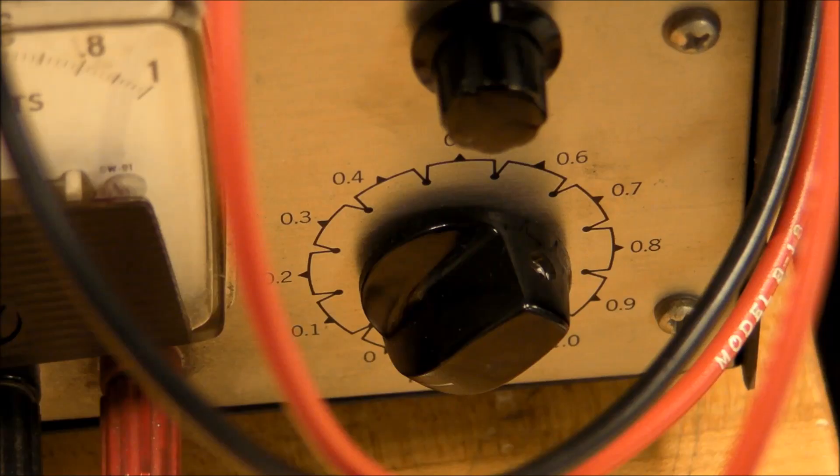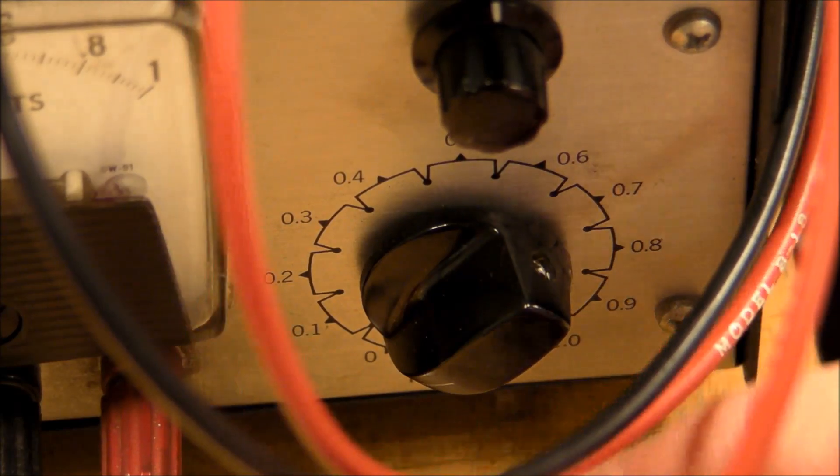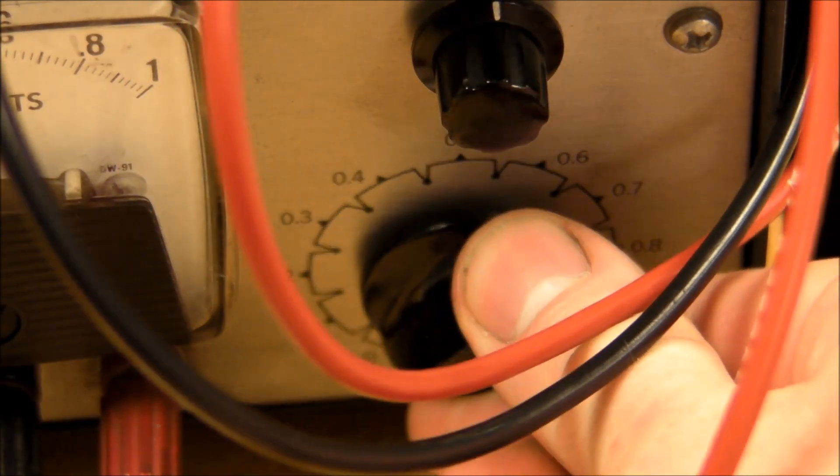Had a little problem there. I got to 125 volts and that was the end of the range. So let me, I already turned down the fine adjust knob, so I'm gonna crank up the range switch to the next range of 0.1 to 0.2 KV.